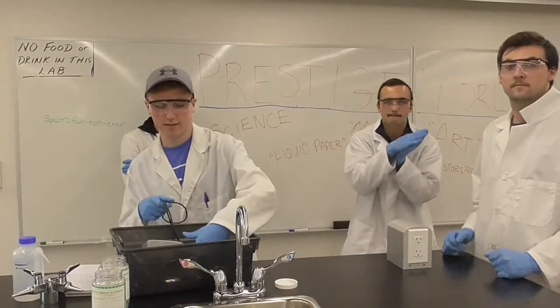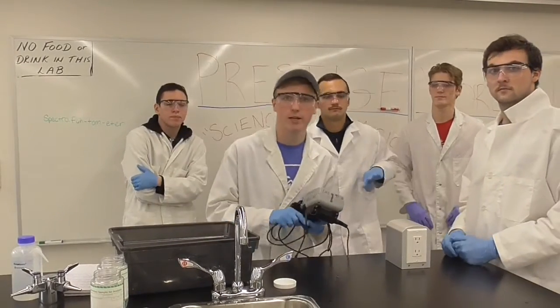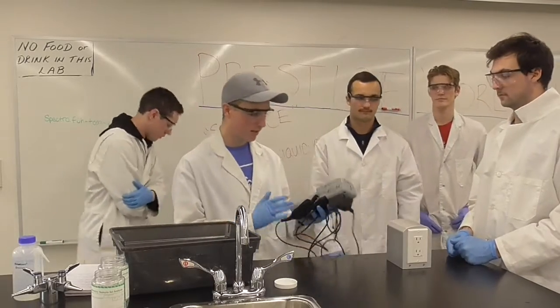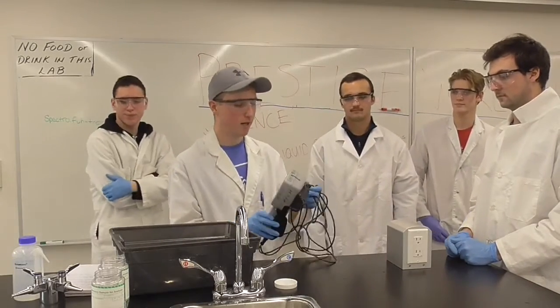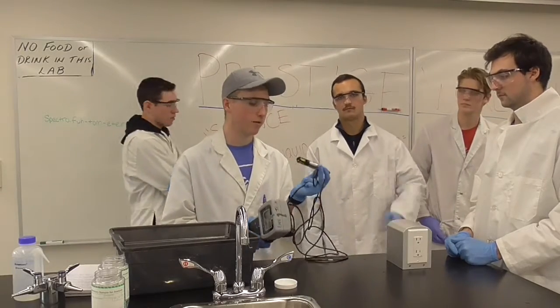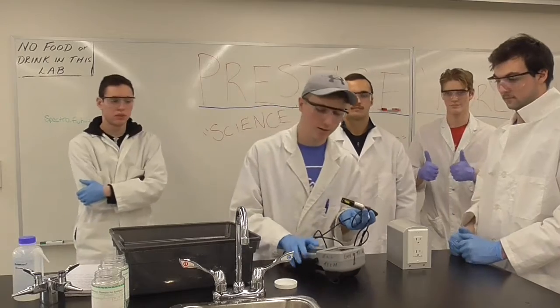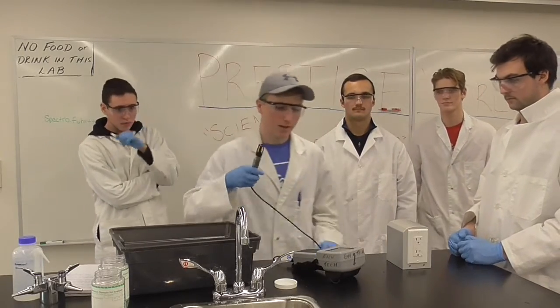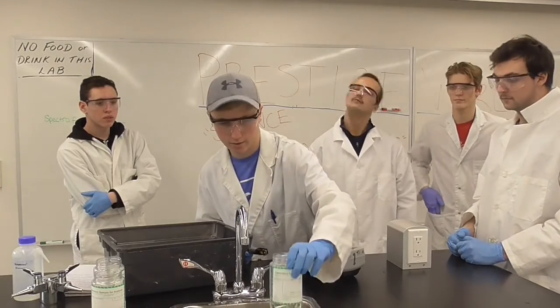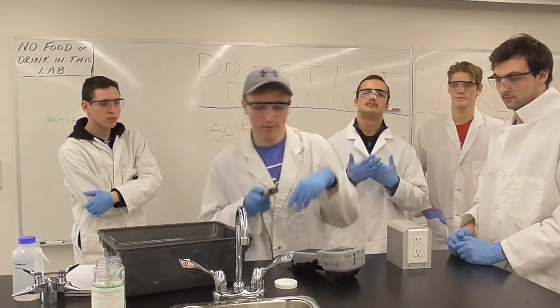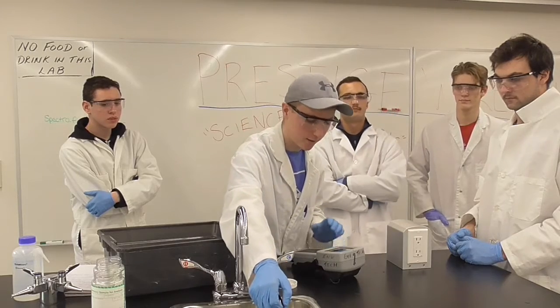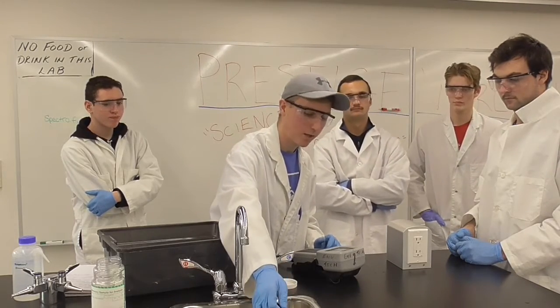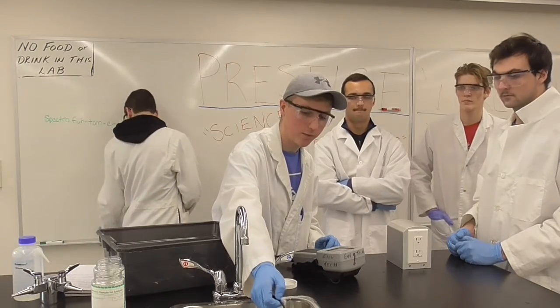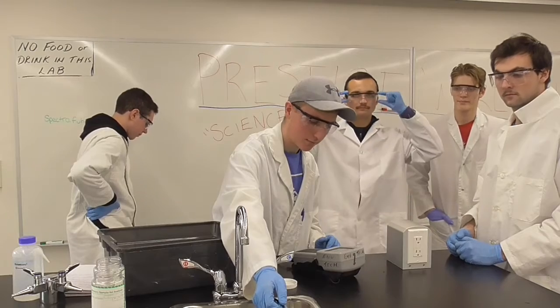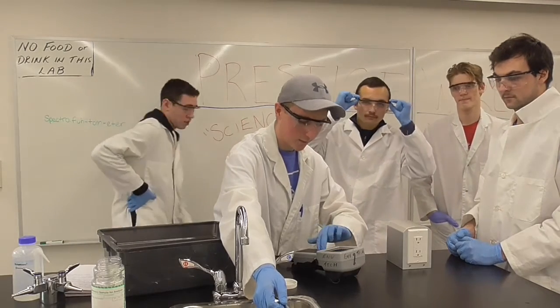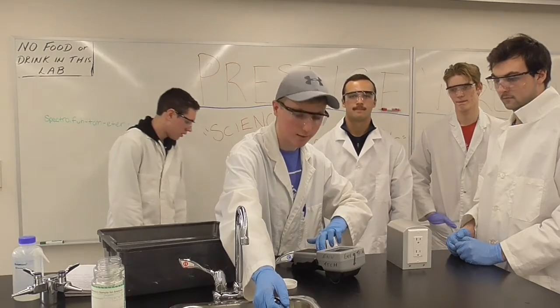Okay, so this is the dissolved oxygen meter. Before we turn it on, we gotta check for 2 things. First, make sure there's nothing broken here. It's looking pretty good. And we gotta check that the probe is in proper working order, which it does look like. So I'm gonna go ahead and turn this on, and I'm gonna put it into our tap water here. And I'm gonna wait for the numbers to settle on the screen. But while I'm doing that, I'm gonna slowly bob up and down. So it's holding a steady value here.